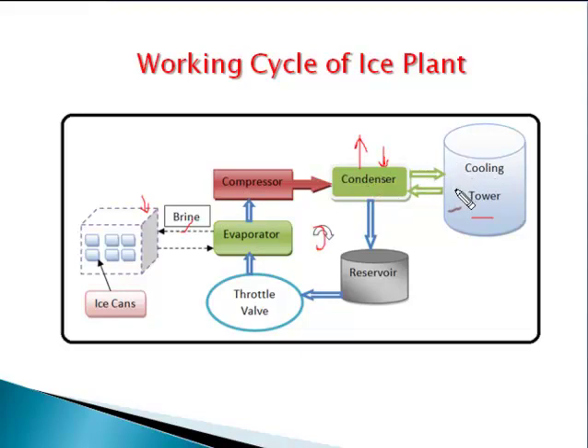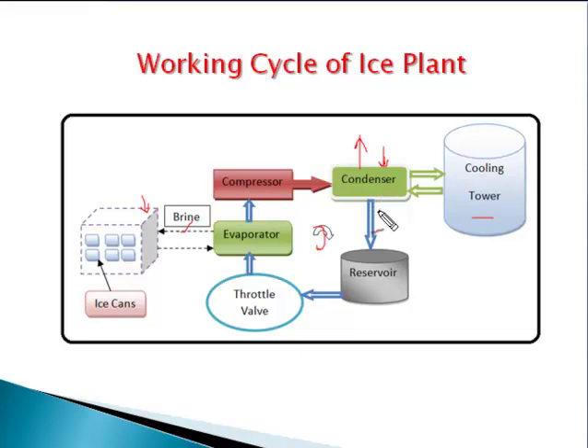Cooling water transfer takes place between the cooling tower and condenser. Water absorbs heat from the condenser and then in the cooling tower that heat is extracted into the atmosphere. After cooling, the primary refrigerant — ammonia — as liquid refrigerant at high pressure is sent to the reservoir. The basic purpose of the reservoir is to ensure that only liquid refrigerant flows into the throttle valve, and never vapor refrigerant.